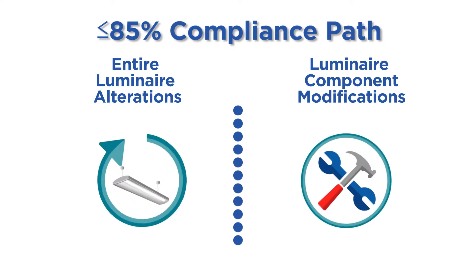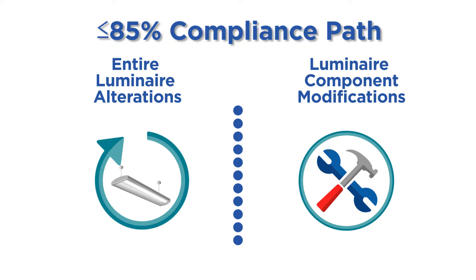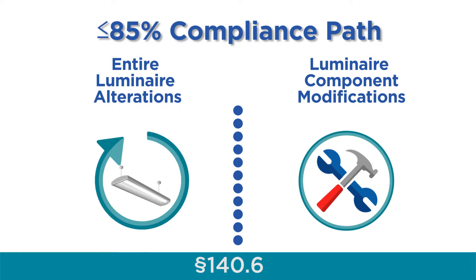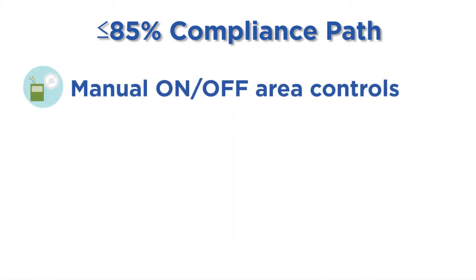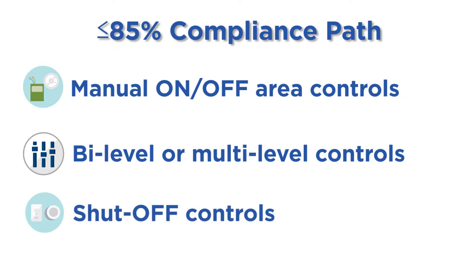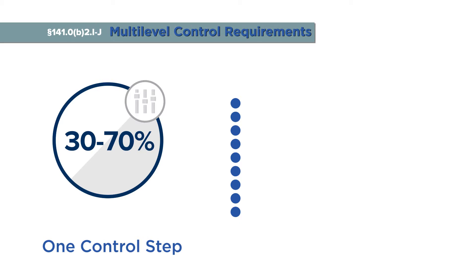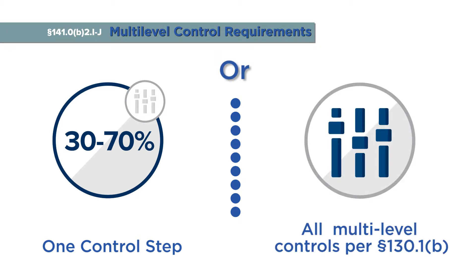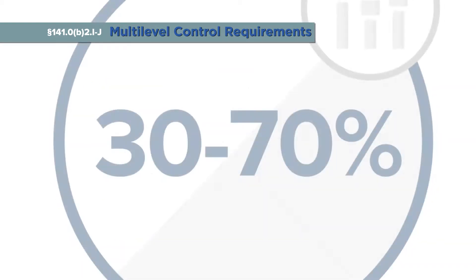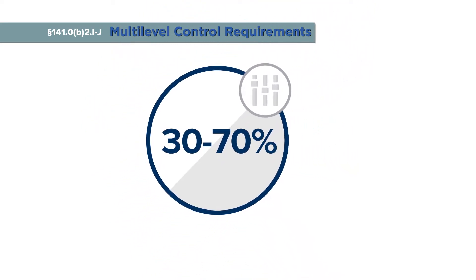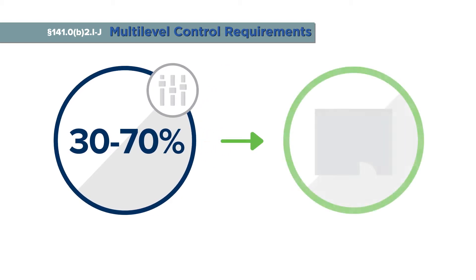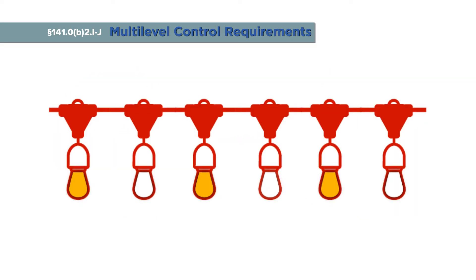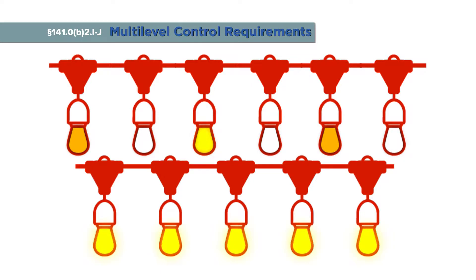The next compliance pathway is available for projects that deliver a total lighting power that is 85% or less of that allowed under the 2016 standards per section 140.6. This compliance option is available for both entire luminaire alterations and luminaire component modifications. Qualifying projects must include manual on-off controls, bi-level or multi-level lighting controls, and shutoff controls. To satisfy multi-level lighting control requirements, the system must provide either one control step between 30% and 70% of full power or meet all multi-level lighting control requirements in section 130.1b. In the 2016 energy standards, this option now applies to the enclosed space and not to each luminaire, meaning that switching alternate luminaires or rows of luminaires can be used to meet multi-level lighting control requirements.